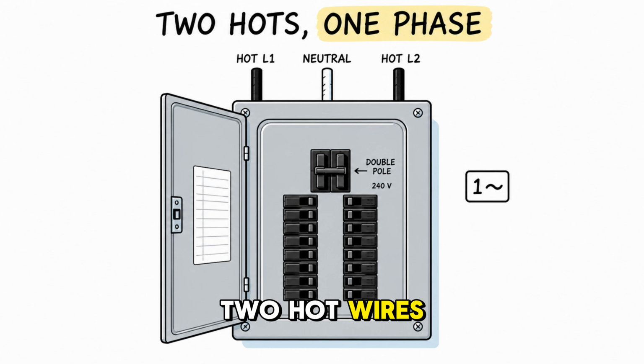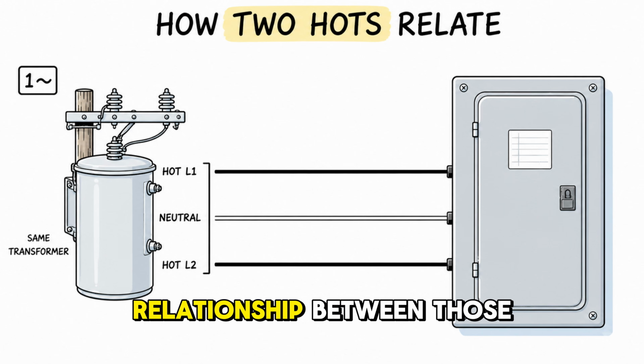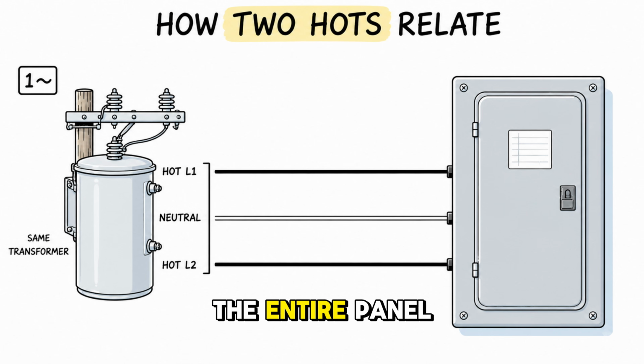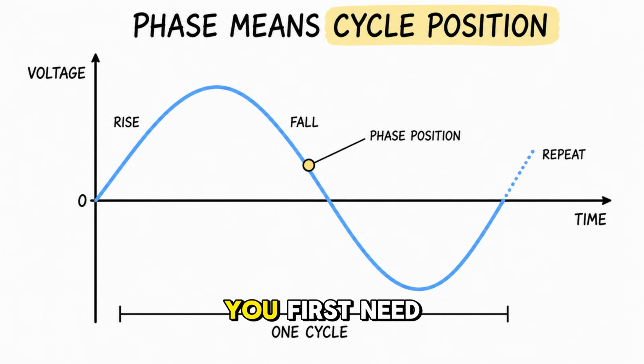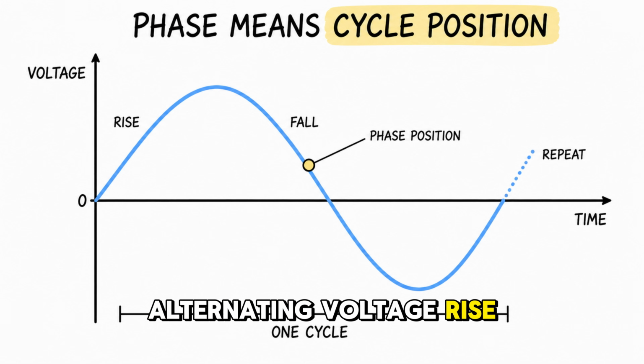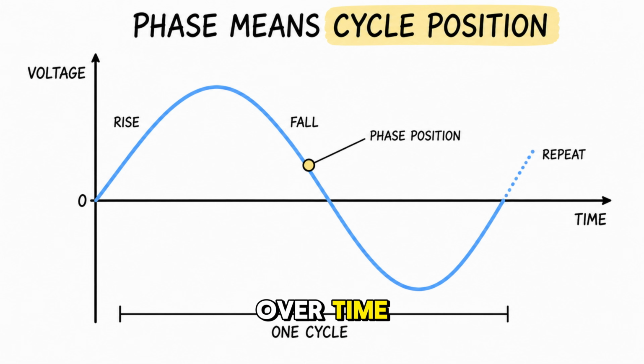You may see 2 hot wires, double pole breakers, and 240-volt circuits, yet the home may still receive only single-phase power. Once you understand the relationship between those 2 hot wires, the entire panel will begin to make sense. To understand how this is possible, you first need to watch alternating voltage rise, fall, and repeat over time. That simple movement will show you what the word phase actually means.